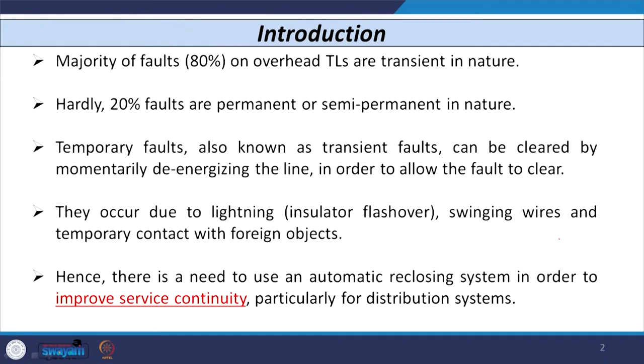In this class, we will discuss the auto reclosing and synchronizing feature, which is useful particularly in the case of protective devices and circuit breakers. We know that the majority of faults — 80 percent — on overhead transmission lines are transient in nature, meaning they may die out after some time. Hardly 20 percent of faults are either permanent or semi-permanent in nature.